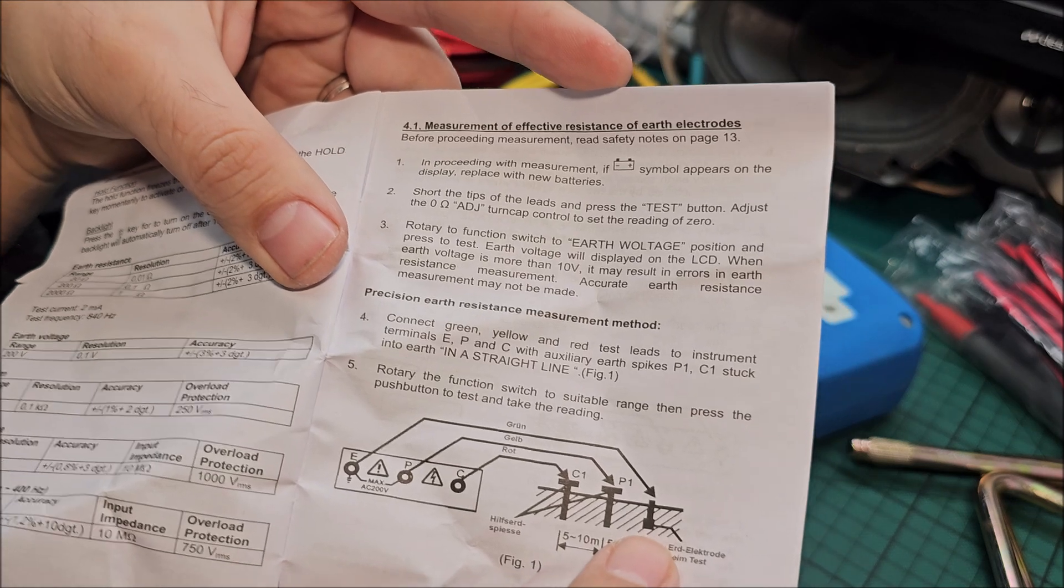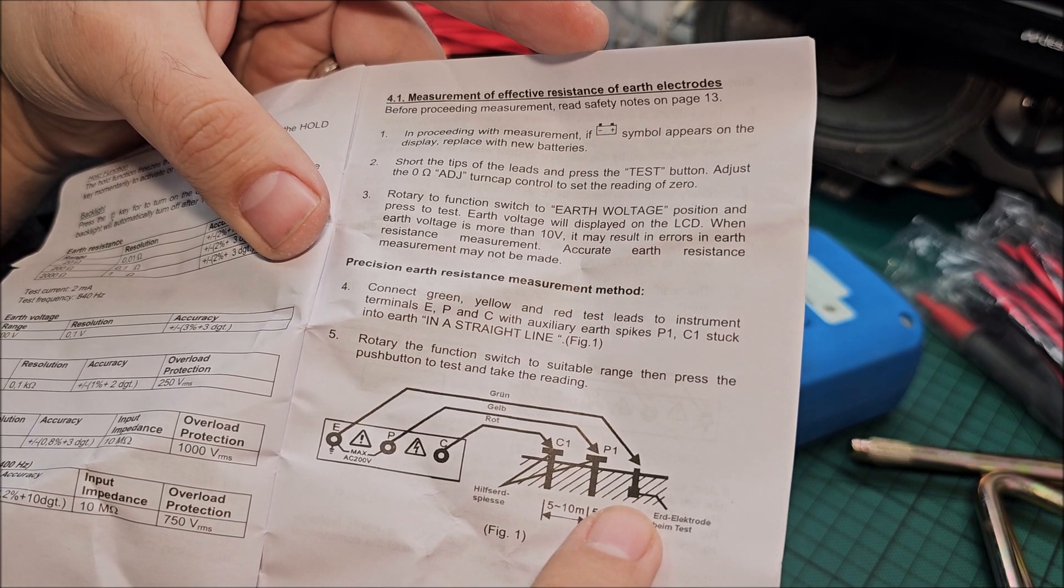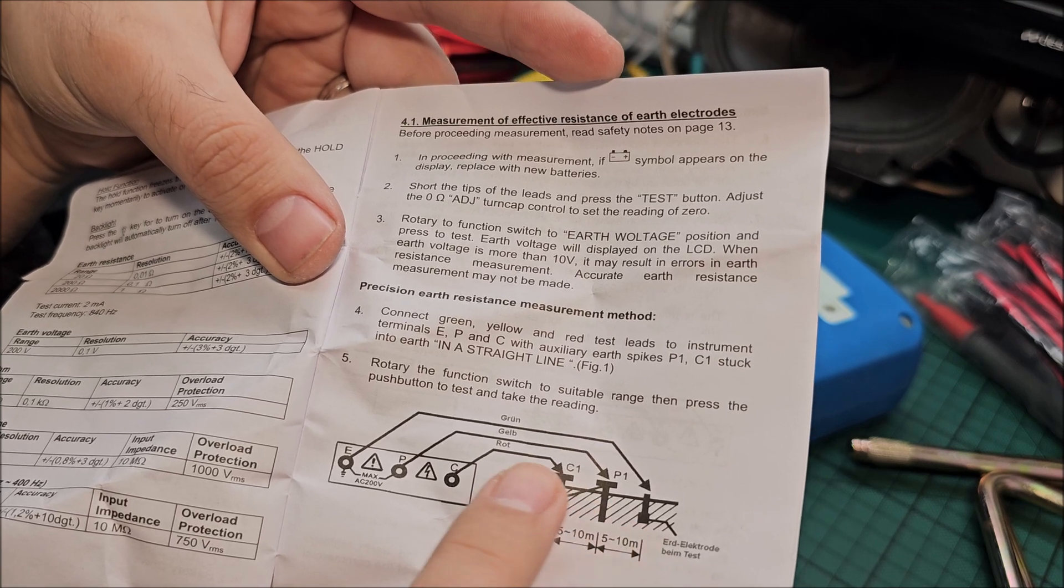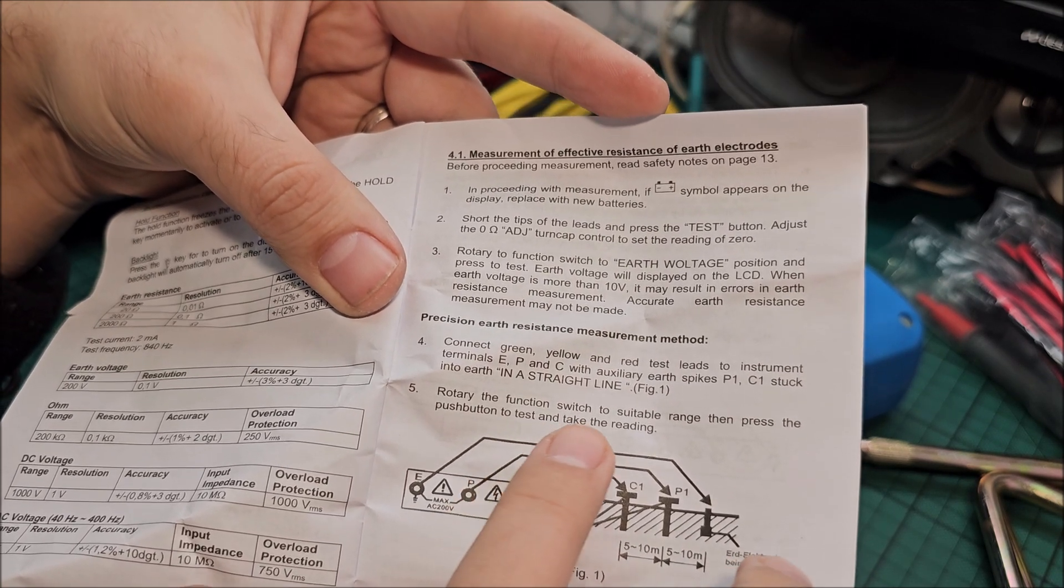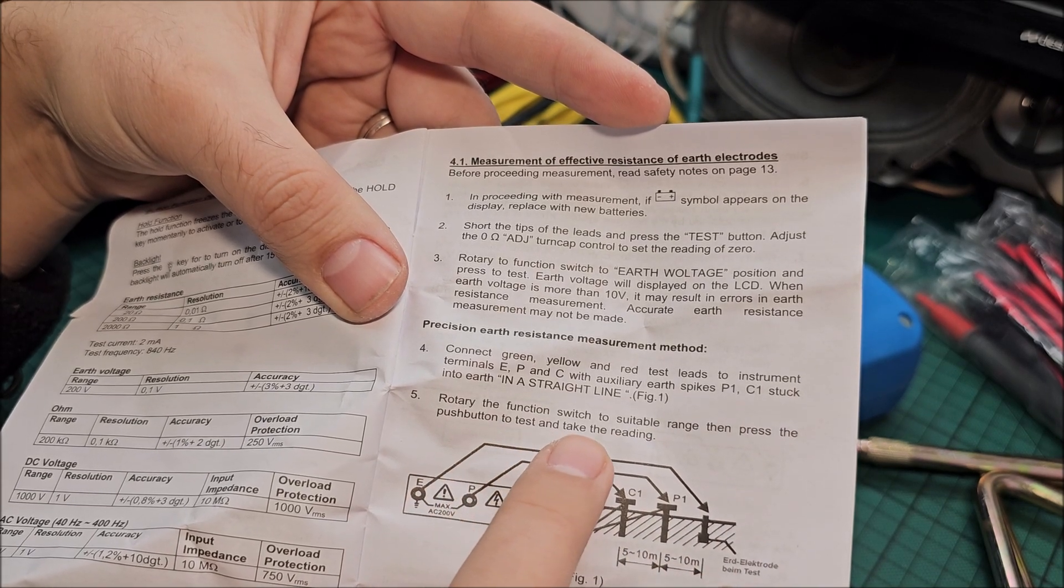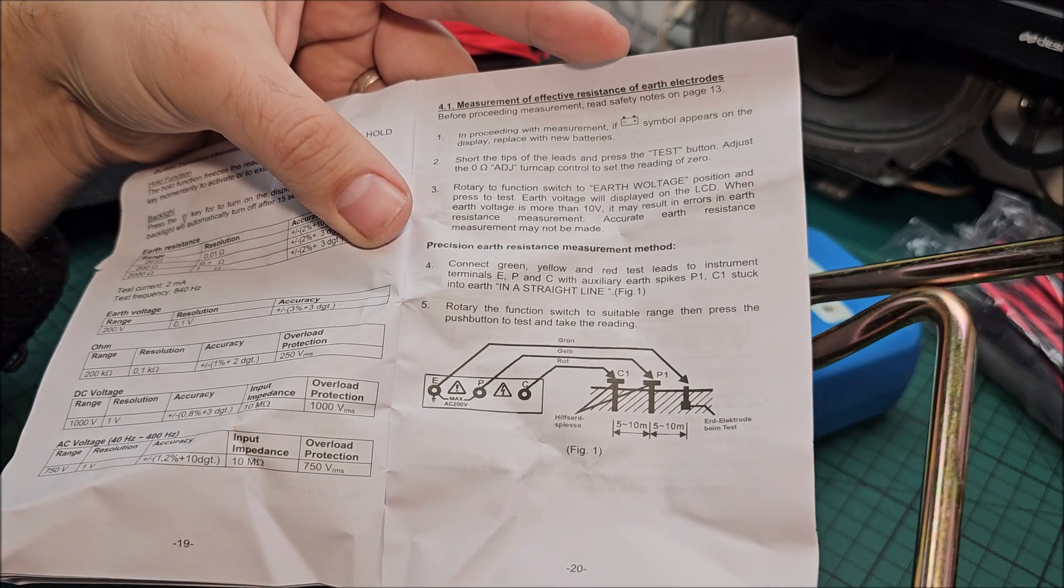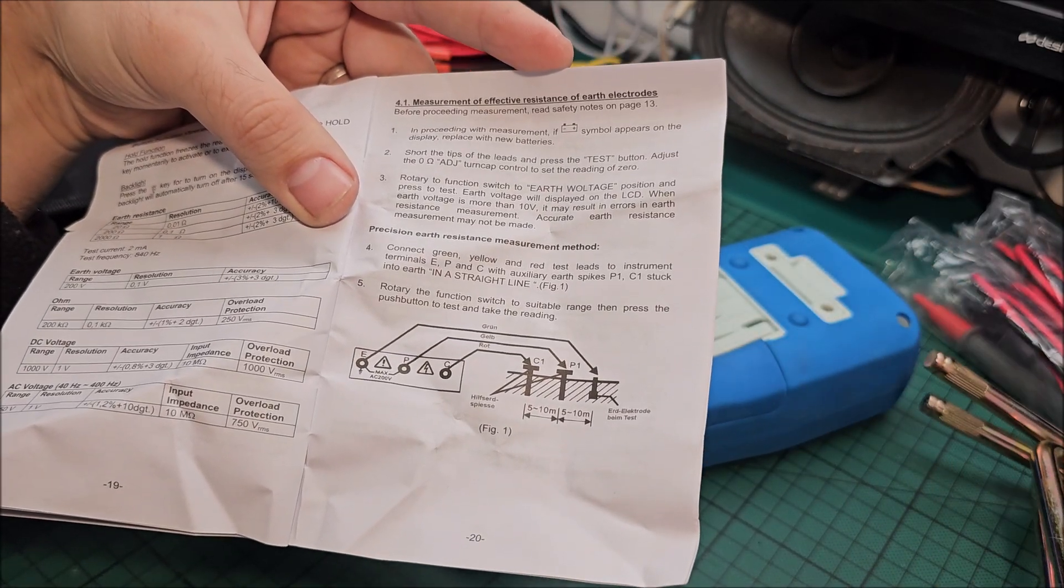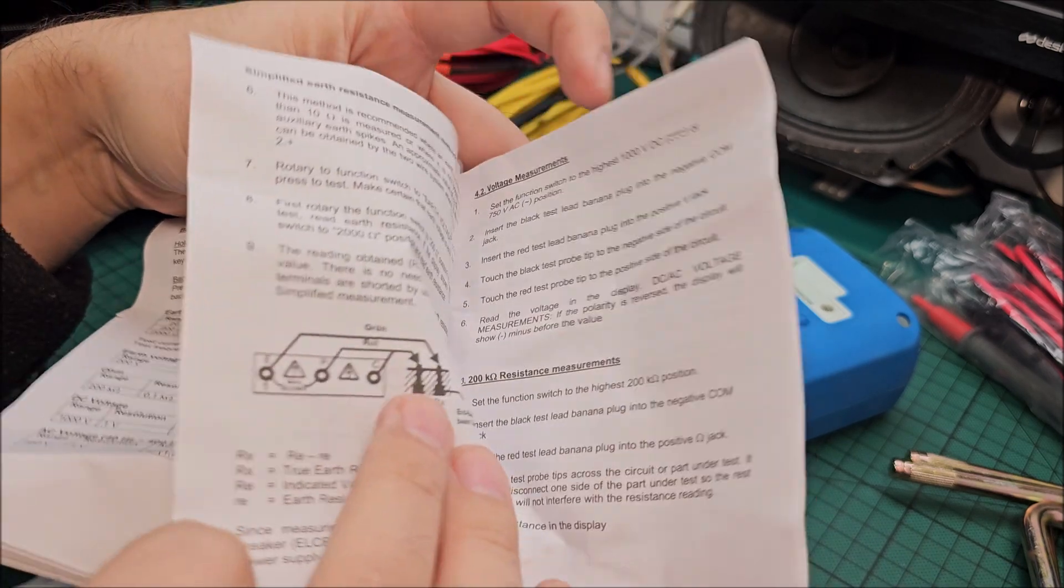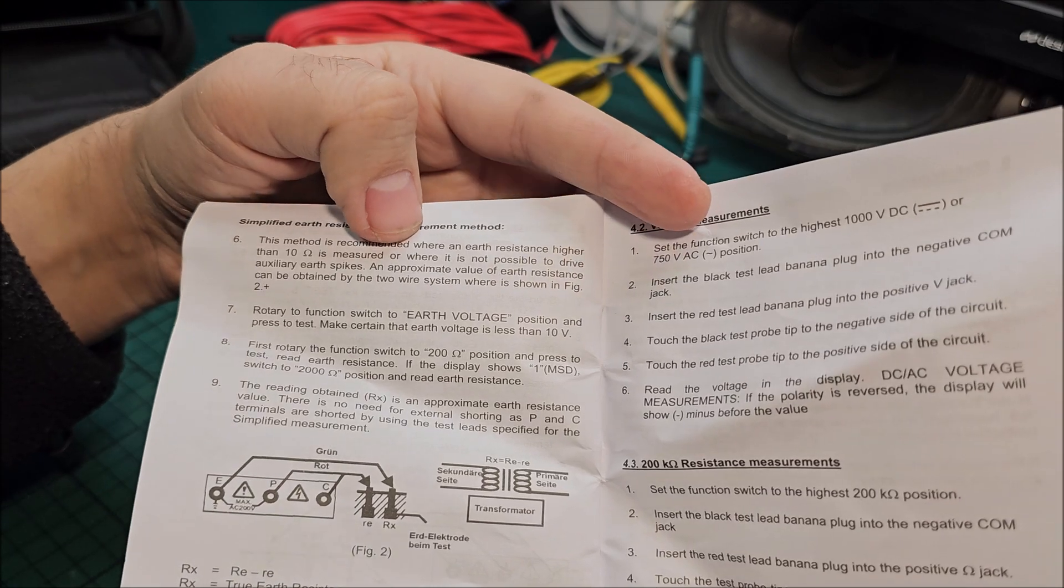Two auxiliary earth spikes stuck in the earth in a straight line. So that's the earth electrode that we need to actually measure. Next to I need to dig a little bit to get next to that one. Suitable range and press to test and take the reading. So red to one of these, yellow to the other one, and green to house electrode basically.